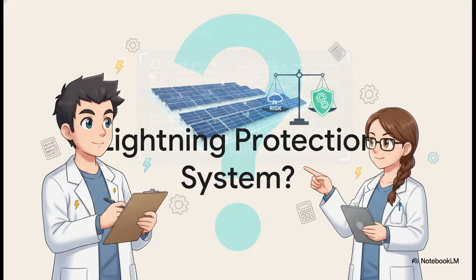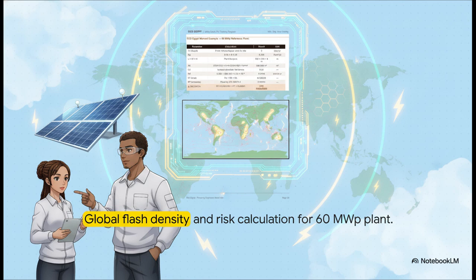strict formula chain. To figure out your dangerous events per year, which we call ND, you're going to need the lightning ground flash density, or NG. You get this by pulling global meteorological data. We're looking specifically at the number of thunderstorm days at your exact site. Take a look at this worked calculation for our 60 megawatt peak reference plant. You take that flash density and multiply it by the physical collection area of your plant. And boom, you start building your real-world risk profile.